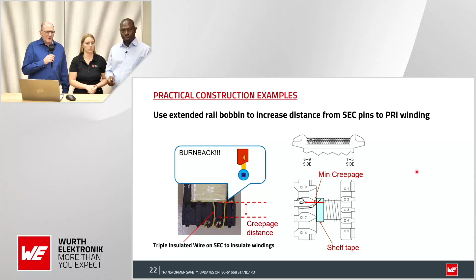Yes. We can show again: with the two-section bobbin construction, when you have fewer turns or fewer windings, the chamber isn't as full, and the distance over the barrier is much longer. This design is done with magnet wire, so the distance from this side to that side is big enough. The shortest path is over the barrier, or directly where the core is mounted to the core. But there are different solutions to increase the distances, such as a special cap that fits in the middle, or over the complete design, so the core is more or less isolated from all the open connections.